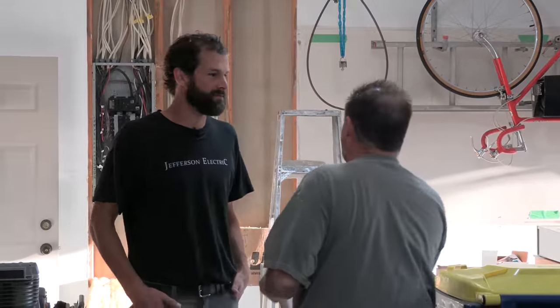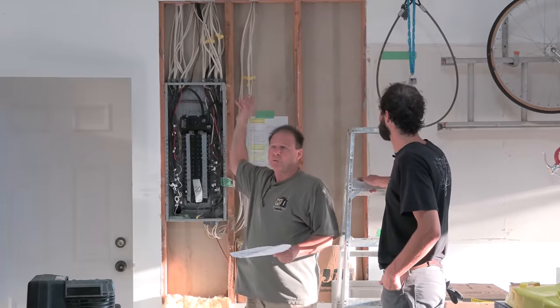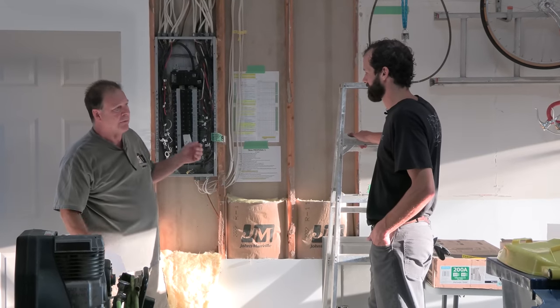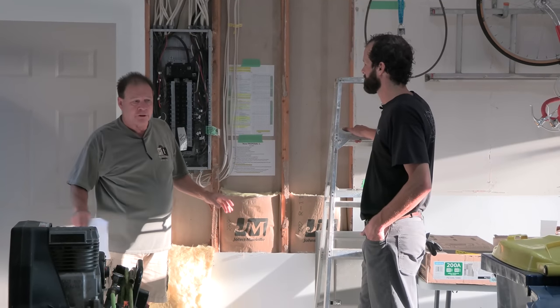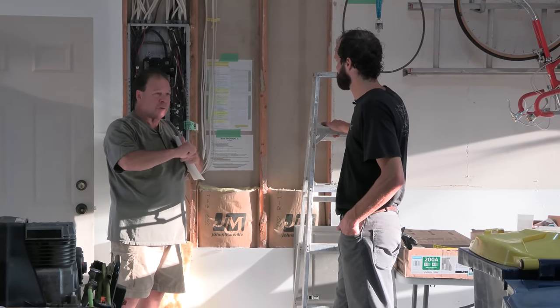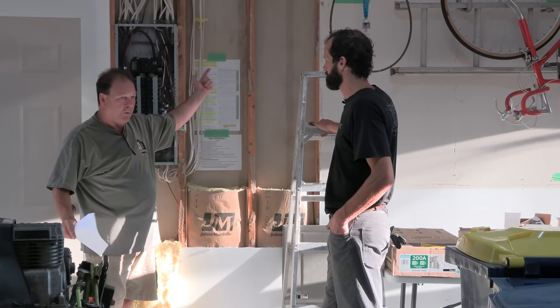You're going to be pulling two-aught — whatever size wire, why not. We've got two sets of wires running way to the other side of the house: one for the 100-amp sub panel and the other going to the generator. Along with that I'm supplying the control cables — a six-wire 600-volt control cable for the Generac, and a two-wire 600-volt that's going to control the air conditioner. So from here for the generator you'll have your generator wire and the two control wires. Once you drop into the basement, the air conditioner wire stays there going out to the AC unit.